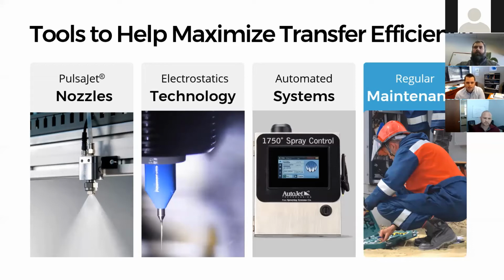Right. So the PulsaJet line has an electrically actuated valve that is controlling opening and closing very rapidly at the nozzles. We can control, based on the width of a pan that comes through or the amount of volume that we want to provide, the amount of width we want to hit, and change how fast we open and close that valve, how much time that valve stays open versus closed, to maintain the right target width that we're trying to hit. In traditional hydraulic nozzles that we wouldn't electrically actuate like this, if you reduce your pressure and your flow, you're going to get different widths of the spray. So we can still control that width and adjust flow rate through the speed of actuation.